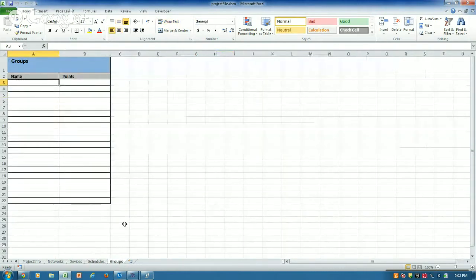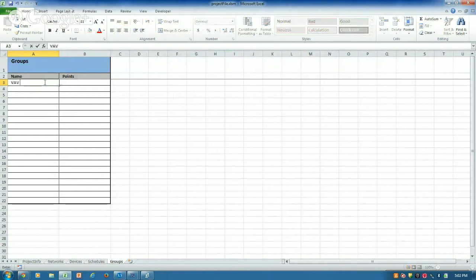Let's say you wanted to put all VAV box flows into one folder. I'll go VAV flows, and the point type is SA-F—that's the point name for a VAV controller. This bucket will be created as a folder titled VAV flow, containing the flow set points, or flow CFM, for each of those boxes.